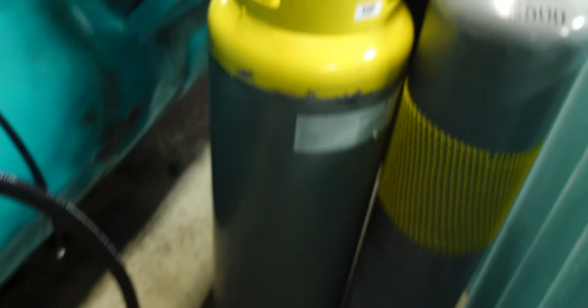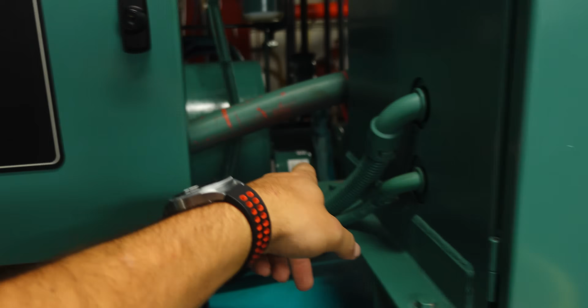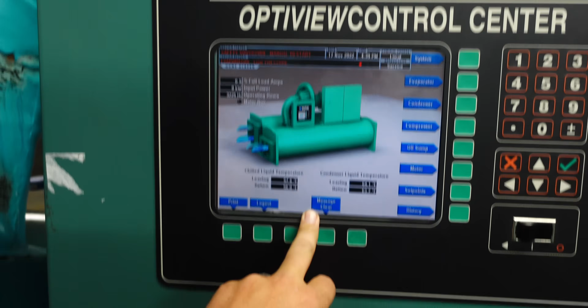From there, disconnects on. We're going to turn this disconnect on. One of our goals is we need to make sure we get power to the machine, so we can verify all the sensors we had to change, and we want to get that oil heater going. If we're doing startup tomorrow morning or by lunch, we've got to get our oil up to temperature. Everything looks fine so far.